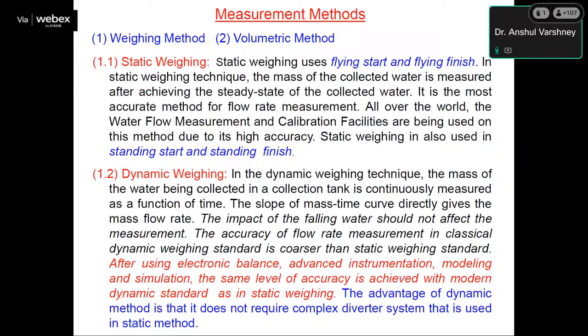Static weighing uses flying start and flying finish. In the static weighing technique, the mass of the collected water is measured after achieving the steady state of the collected water. It is the most accurate method for flow measurement all over the world. The water flow measurement and calibration facilities use this method due to its high accuracy. Static weighing is also used in standing start and standing finish.